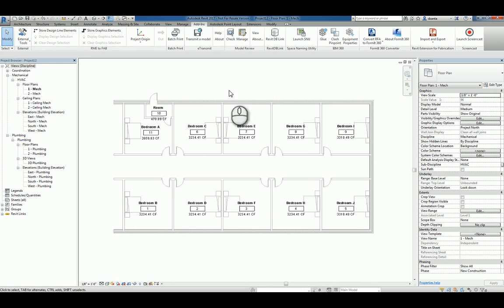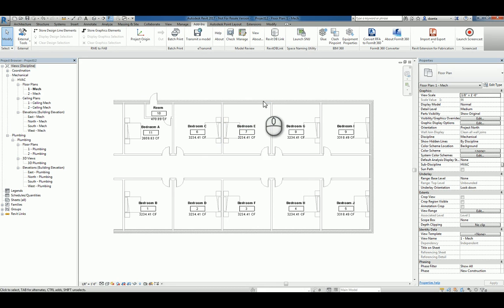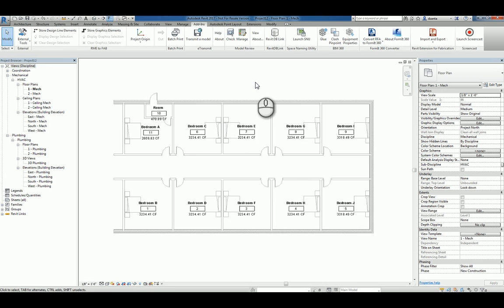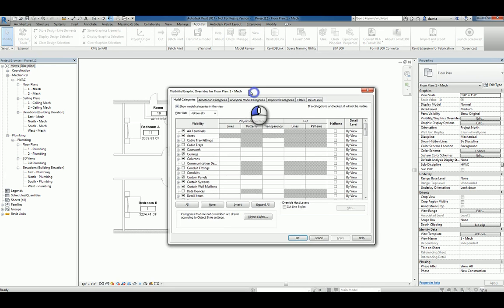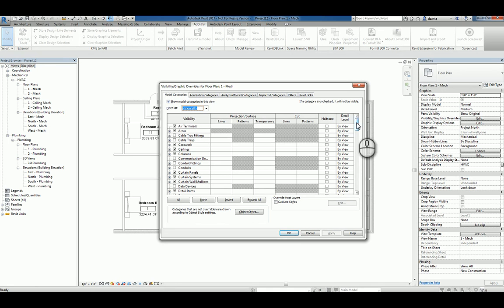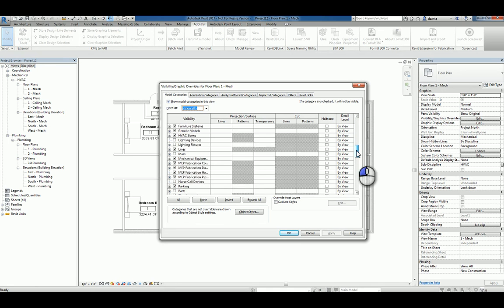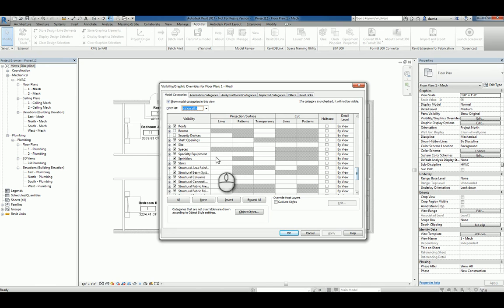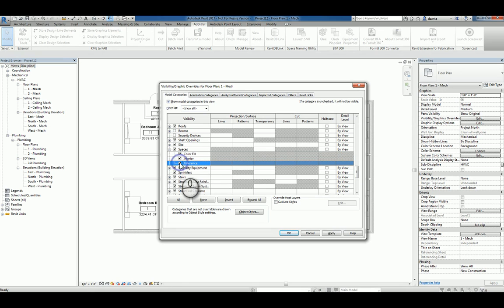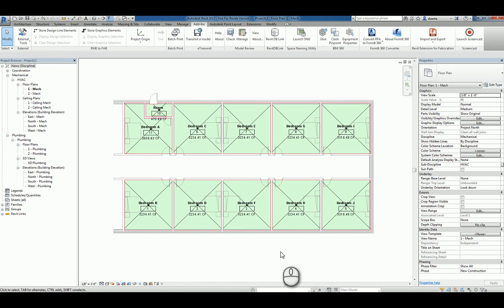Now that we have the spaces placed, if we need to select them, you'll notice that the reference lines that are in X are kind of hard to see. If I open up the visibility graphics dialog box by typing in VV or VG, make sure you filter list shows MEP content and scroll down to spaces. If you expand spaces, you can see you can put a check mark for interior and reference. Interior and reference allows you to see the data a little easier and easier for you to select. This is how you create spaces in Revit MEP 2017 or just Revit 2017.